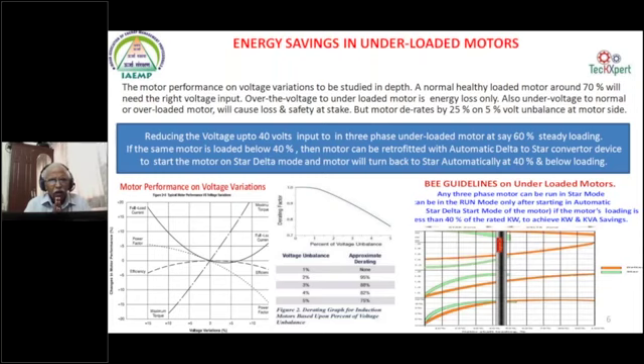So, energy savings in the underloaded motors. Let us say I am getting 415 volt on the EB. I have an on-load tap changer transformer, and I am limiting the number of tappings that change per day. At the same time, I am keeping an optimum band of transformer secondary voltage between, let us say, 410 to 420 volt. It is operating at a band of 10 to 15 volt, let us say.